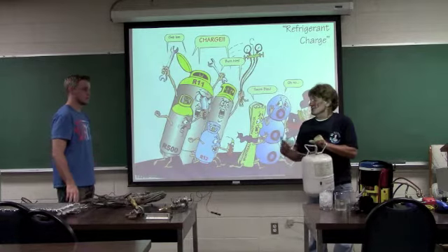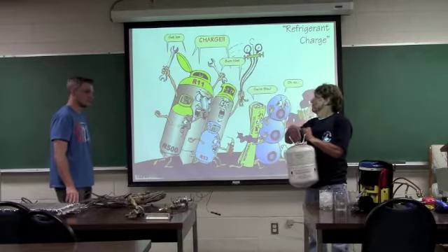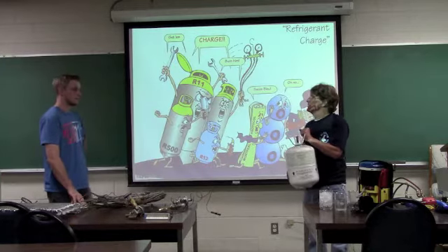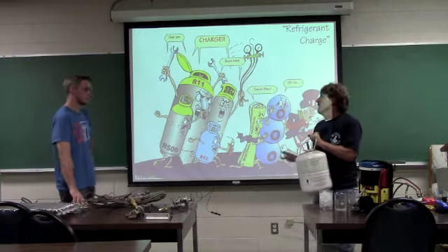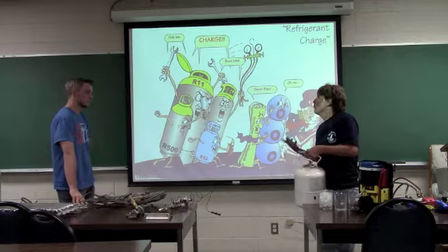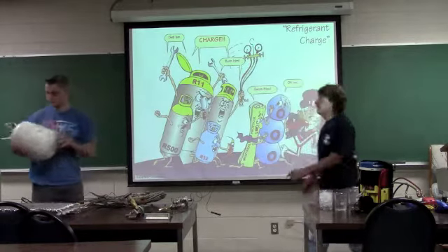As long as the pressures and temperatures have equalized, and there's both liquid and gas there, if I measure the pressure, I can know what the temperature is. If I know what the temperature is, I can plot the pressure. Correct. And if I know both of them, I can actually determine what the refrigerant is. So is it just this one? No, it's for multiple refrigerants.